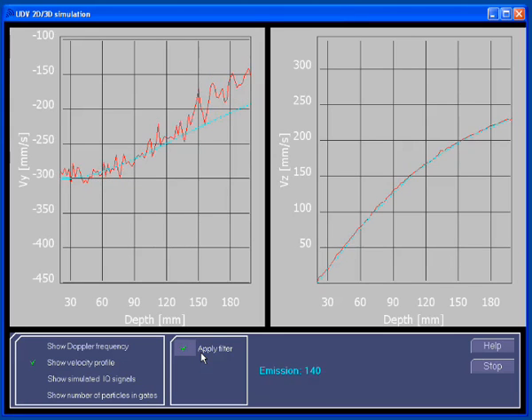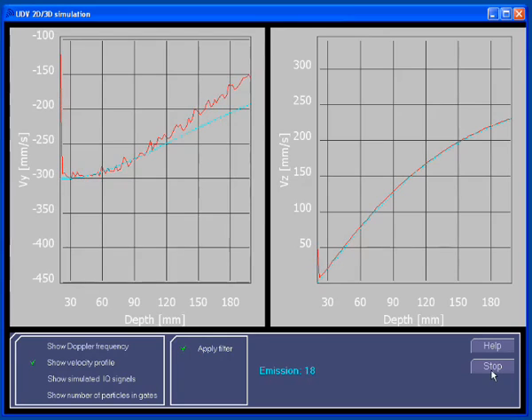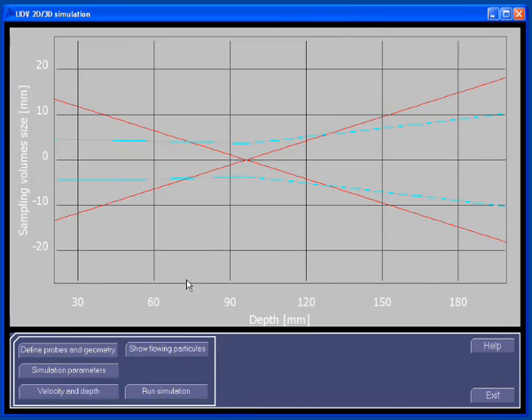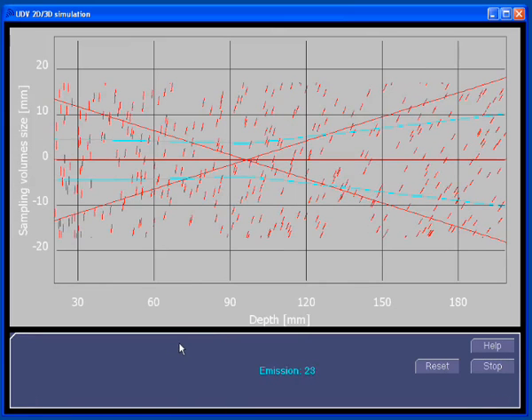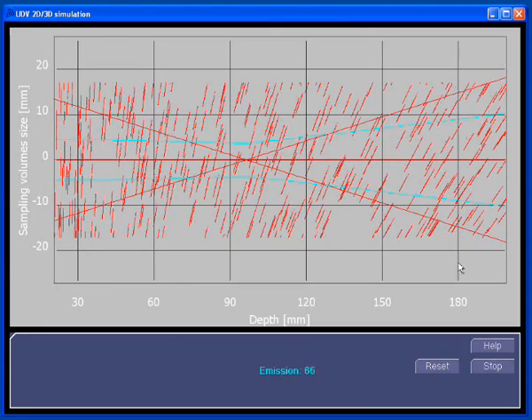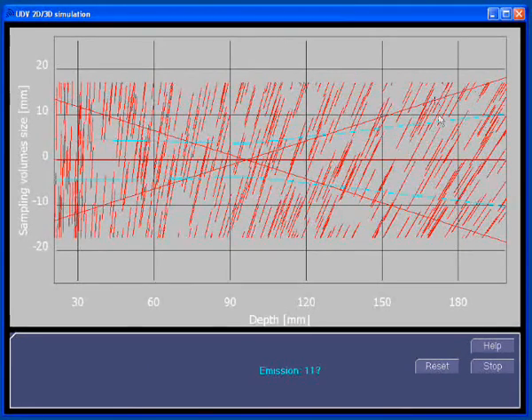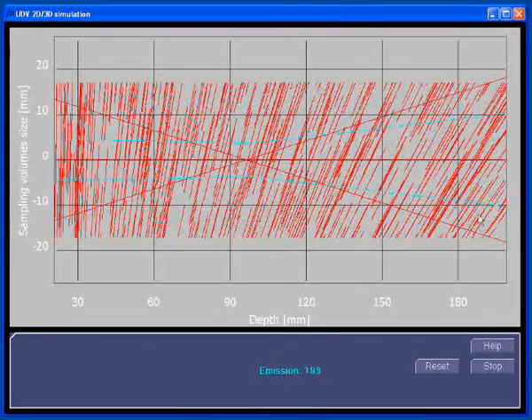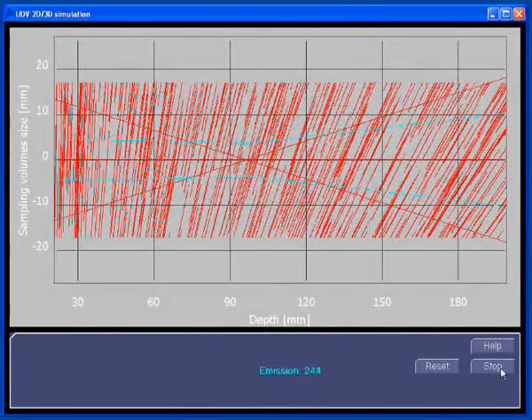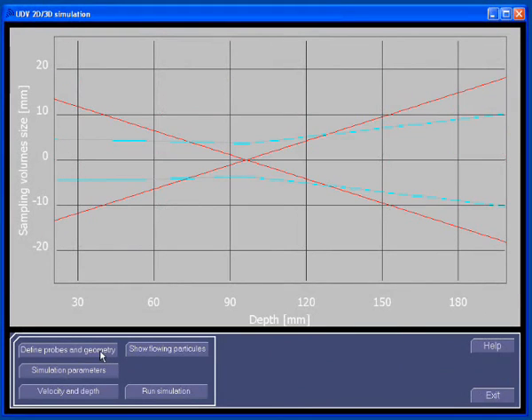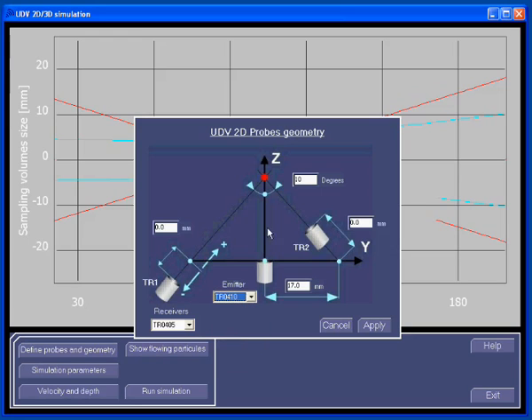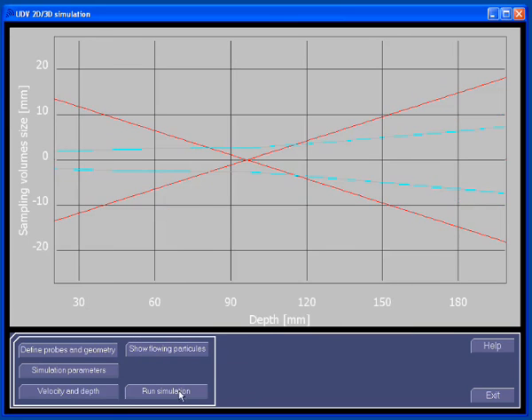Let's apply a filter. As you may realize, the VY component is not correctly measured at higher depths. The reason is that the simulation software assumes that all particles belonging to a single sampling volume must have the same velocity. If you have a closer look at the flowing particles, you will realize that particles flowing in this region do not have the same velocities as in that region. The way to improve this is to reduce the size of the sampling volume by changing the emitting probe. Let's take a 4 MHz 10 mm probe which has a narrow beam. Now the Doppler frequencies are also well measured and we have a little improvement in the velocity profile.